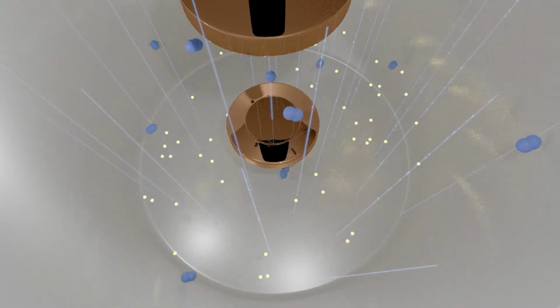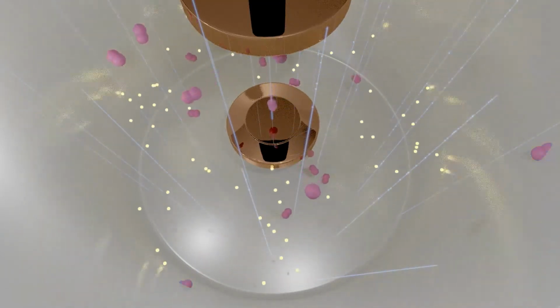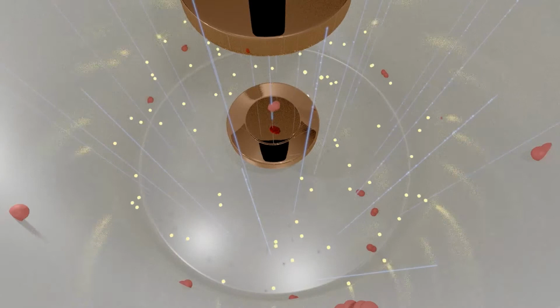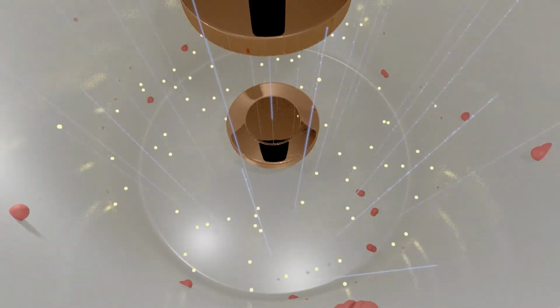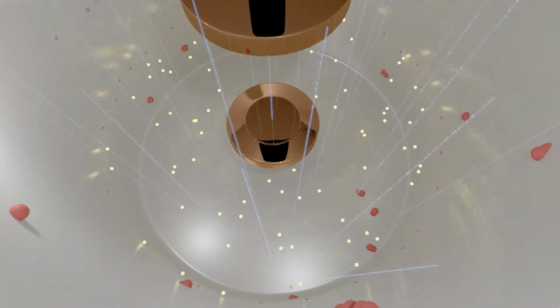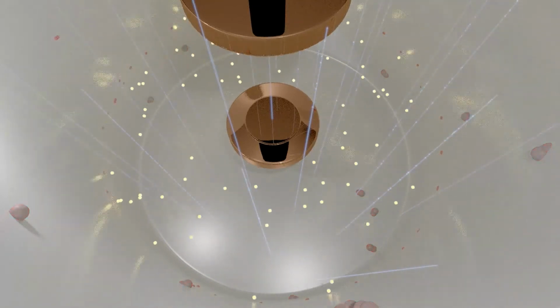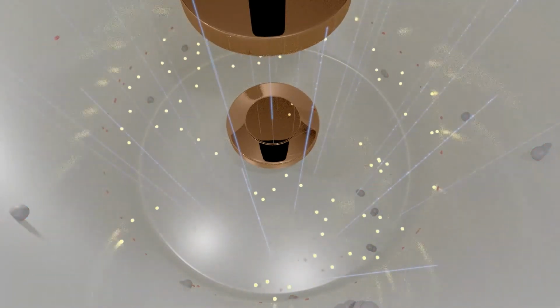The third thing that happens is two unstable gas molecules hit each other and combine. When they do that, two have become one, so we again have lowered the pressure inside the vacuum interrupter. So we've tarnished or oxidized some of the gas molecules, converting them to solids. They're no longer a gas, they're simply tarnishing the copper inside the interrupter, which does not affect the interrupter's operation in any way. This has lowered the pressure. We've combined some, and that has lowered the pressure. But some have become trapped behind shields and other things, and we can't get to them.